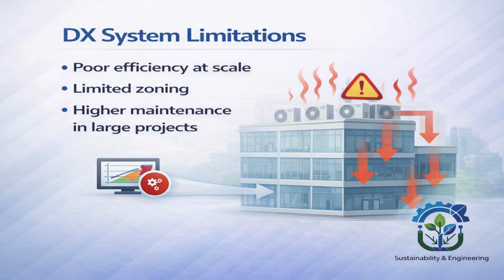The second limitation for DX systems is limited zoning. With DX systems, zoning flexibility is restricted. One outdoor unit usually serves one indoor unit, or at best, a very small group. This makes it difficult to handle different occupancy patterns, different heat loads, and different operating schedules. As a result, some areas become overcooled while others remain uncomfortable.